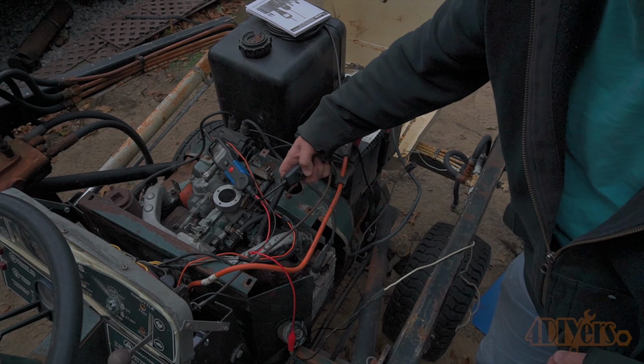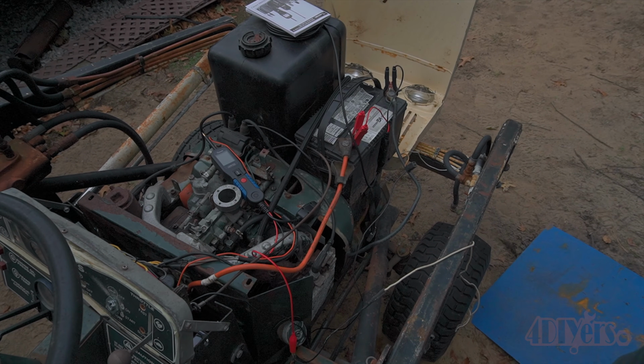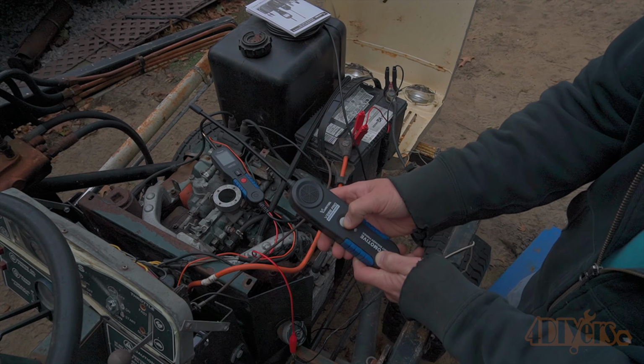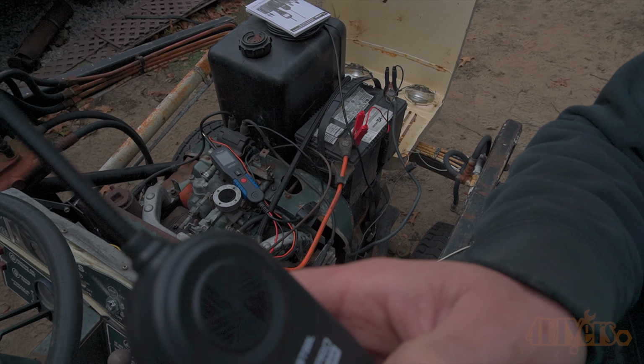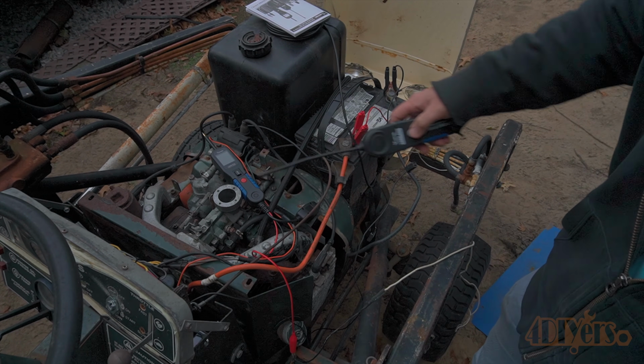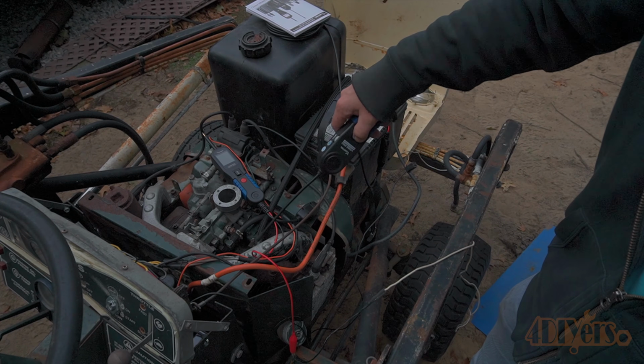Then turn the tester into position 2. Now with the breaker tester, rotate the wheel on the side to the on position. You may need to select the sensitivity.